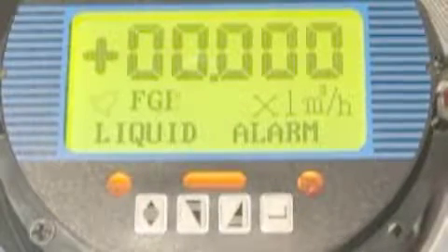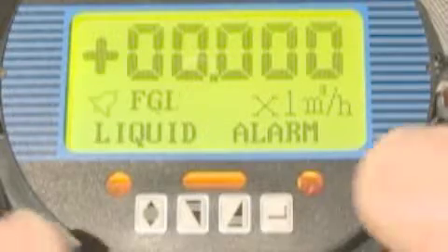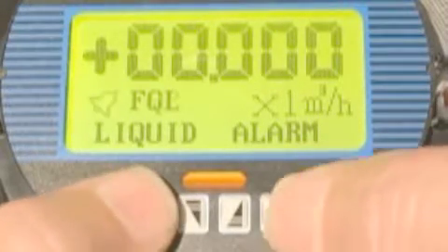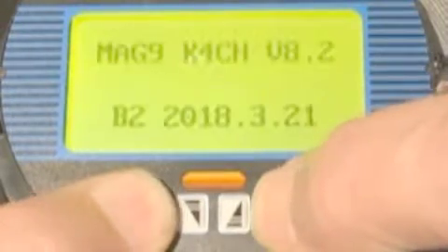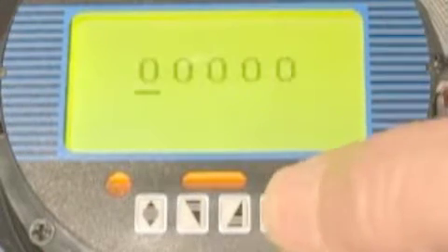When you first get your meter, what you'll want to do is discover what the current settings are. The way to do it is we press the two outer buttons simultaneously. We let the sign of it come through. When we see parameters set, we click enter.